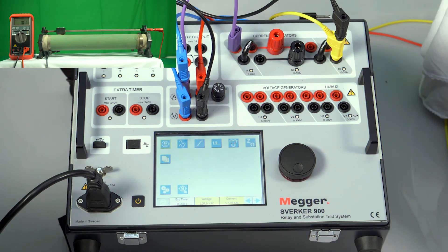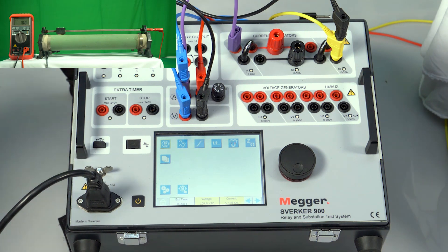Now let us connect the current generators in series so that the compliance voltage would get added and we will be able to get a very high burden. Let us connect to 20 ohms resistance and inject approximately 5.5 amps.